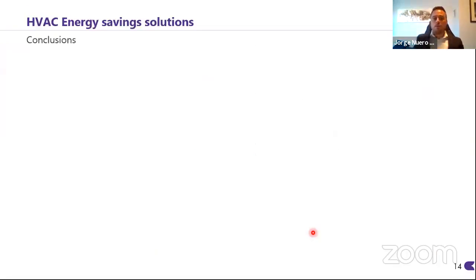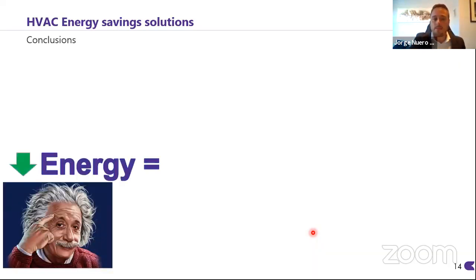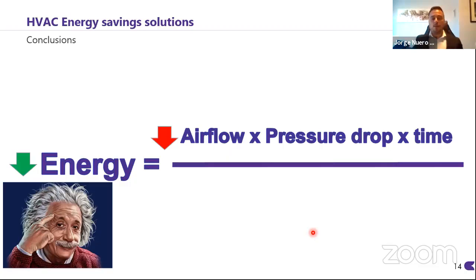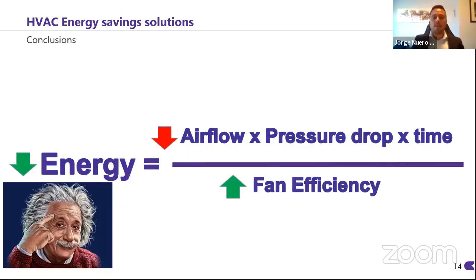So, as a conclusion in this chapter, before going to the next one, how can we save energy in our system? We can save by using this very simple formula. If we reduce the airflow, or if we reduce the pressure drop, or we reduce the time that the installation is running, for example, using an eco mode during the night or during the weekend when there is no production, and increasing the efficiency of the fans, we can drastically reduce the amount of energy that we need to dedicate to the HVAC system, heating, ventilation, air conditioning.